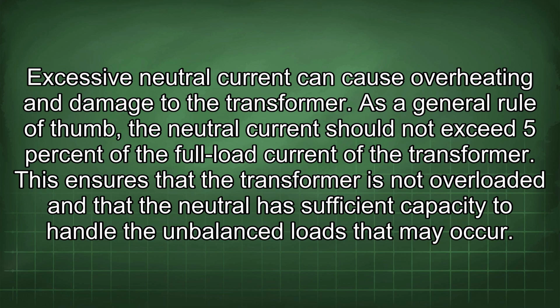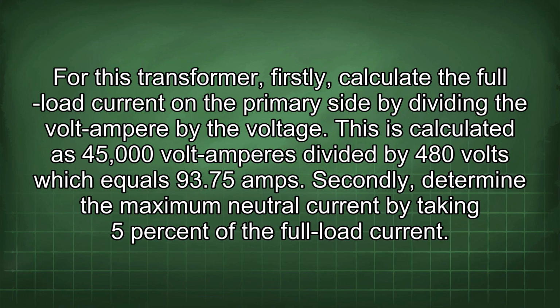As a general rule of thumb, the neutral current should not exceed 5% of the full load current of the transformer. This ensures that the transformer is not overloaded and that the neutral has sufficient capacity to handle the unbalanced loads that may occur. For this transformer, firstly calculate the full load current on the primary side by dividing the volt-ampere by the voltage. This is calculated as 45,000 volt-amperes divided by 480 volts, which equals 93.75 amps.